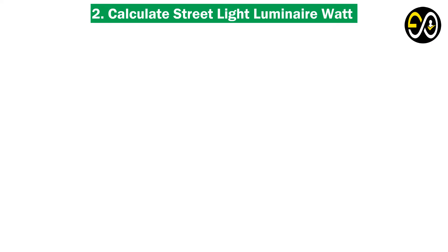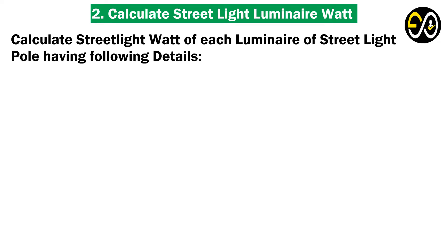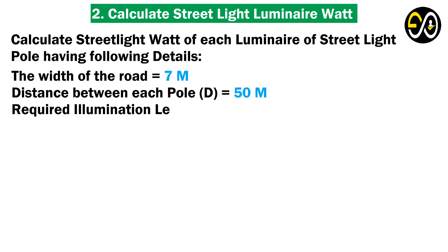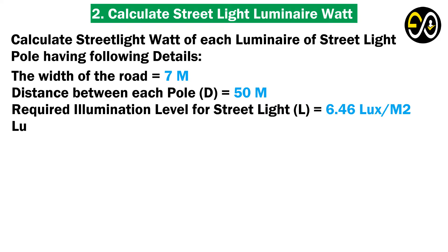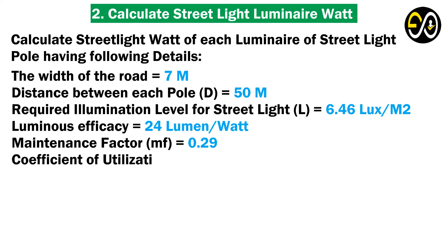Example 2: Calculate the watt of each luminaire of a street light pole given the following details. The width of the road equals 7 meters. Distance between each pole D equals 50 meters. Required illumination level for street light L equals 6.46 lux per square meter. Luminous efficacy is 24 lumens per watt. Maintenance factor MF equals 0.29. Coefficient of utilization factor CU equals 0.9.